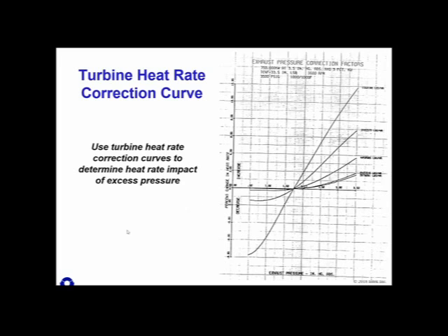And so the way to use this, oh, by the way, we do have somebody in the class that's looking to build these models, so this is very applicable to what he needs. You would go here and you would create a function, obviously, to do this. You wouldn't do this on paper, but you would create a function that interpolates all this data, and you would find the duty that the condenser is operating at. So in this particular case, 3-point-something million pounds per hour. And this would be the line that we're going to extract information from.